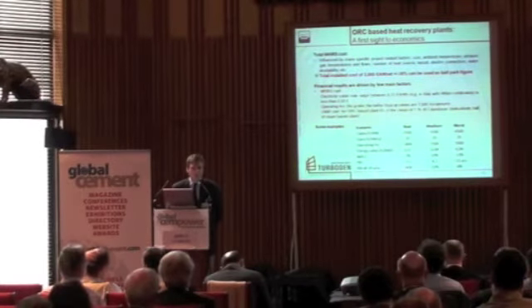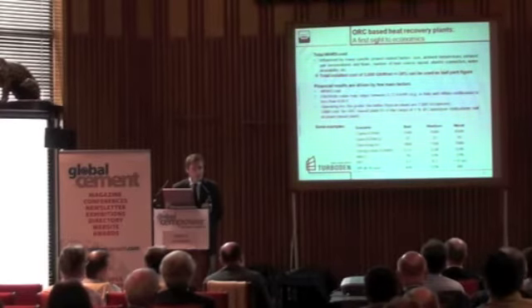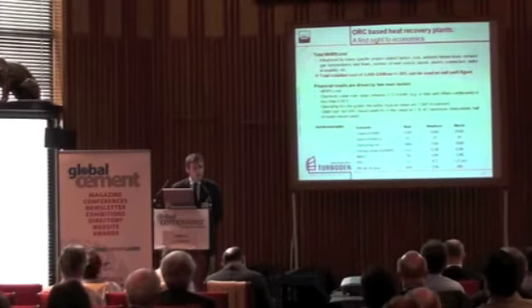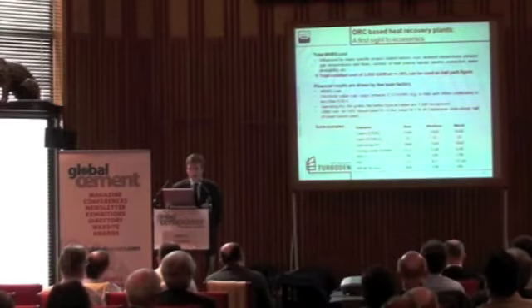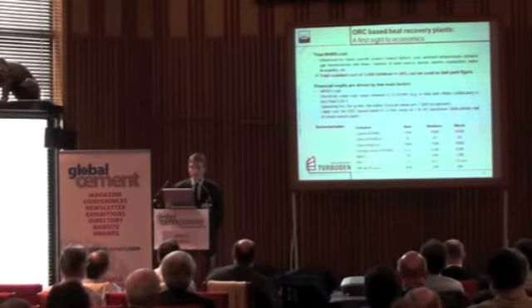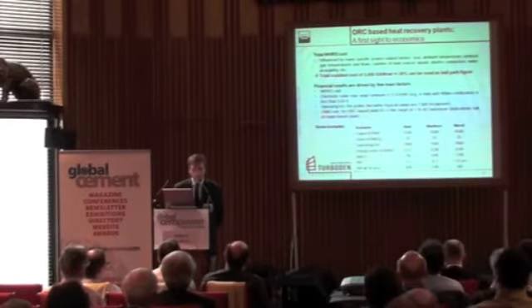Though, just to give a very broad ballpark indication, we are saying a total installed cost could be in the 3,000 euros per kilowatt range, plus or minus 30%. So it is a very broad range, leading in very good cases down to 2,000 euros per kilowatt, and in the worst cases up to even 5,000 euros per kilowatt. So there are namely three main drivers which must be considered when analyzing the financials of waste heat recovery systems.